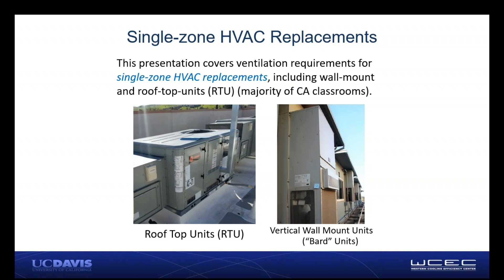Okay, I'm talking specifically here about California ventilation compliance. Hopefully the message can be applied to other states and other regions. California's building energy efficiency standards, Title 24 Part 6, specifies ventilation requirements for the state. HVAC replacements must comply with these standards, even when the replacements are like for like.